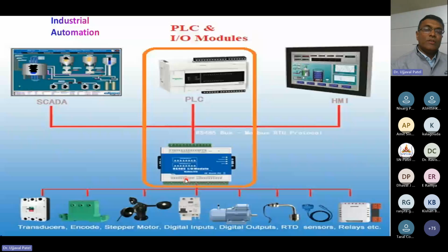This module is called the input-output module, or IO module. The RTD gives input to this IO module, which is used for signal conditioning of the input signals—basic filtering to remove noise from the input signals—and then that filtered signal is applied to a controller.